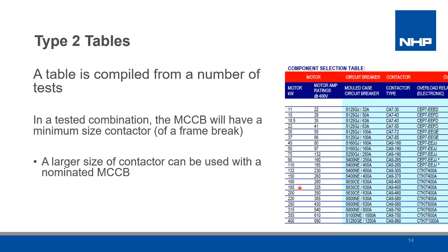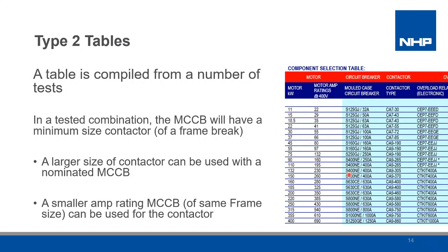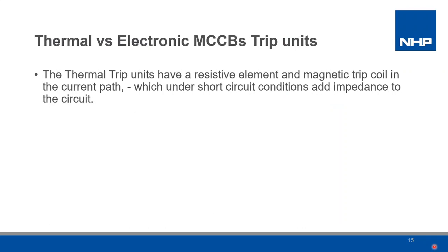An example would be for the 100 amp breaker with testing to a 72 amp contactor, you could utilize the 85 amp contactor without an issue. Or if you're testing with a 63 amp breaker and the 43 amp contactor, you could use a smaller trip unit being 50 amp with that same contactor. Whilst you can change trip ratings, you cannot change trip unit types.